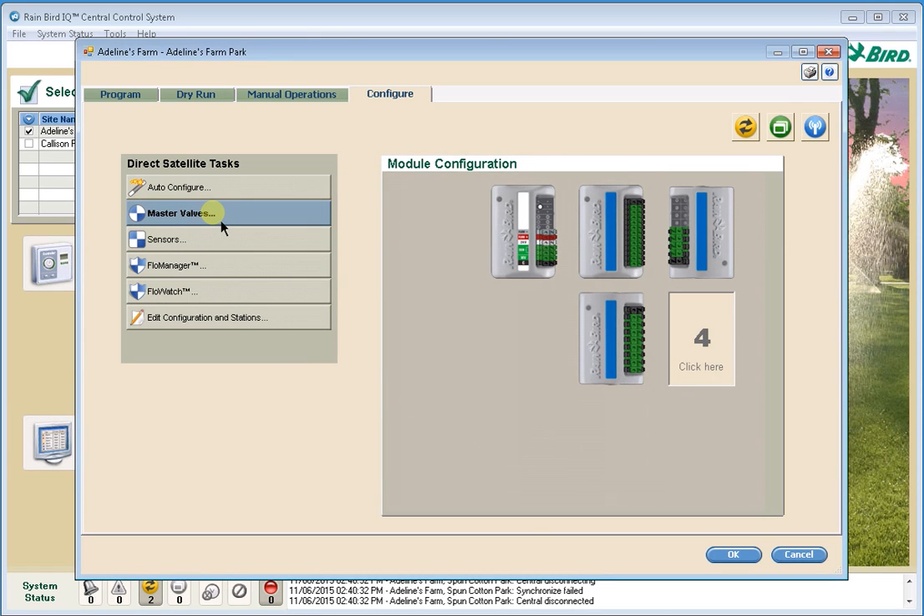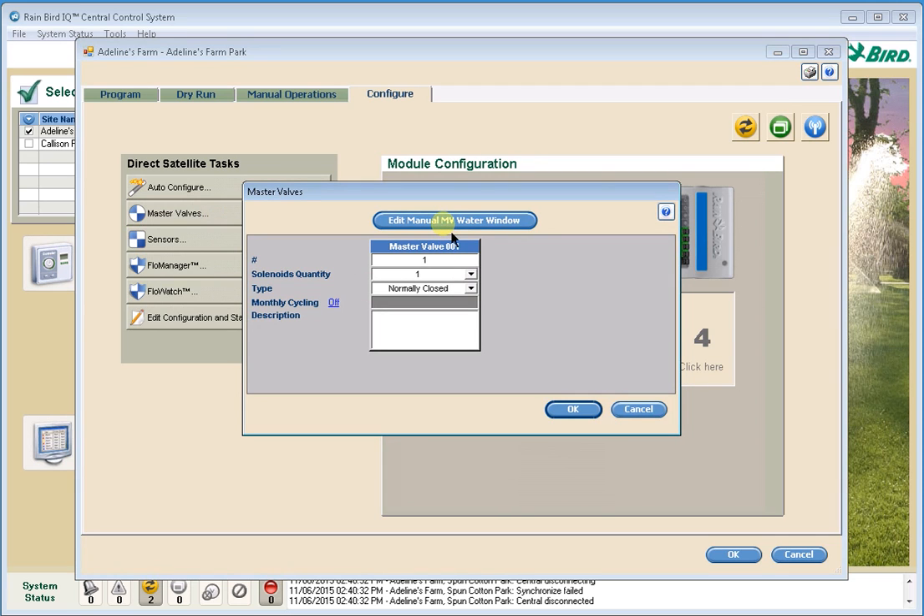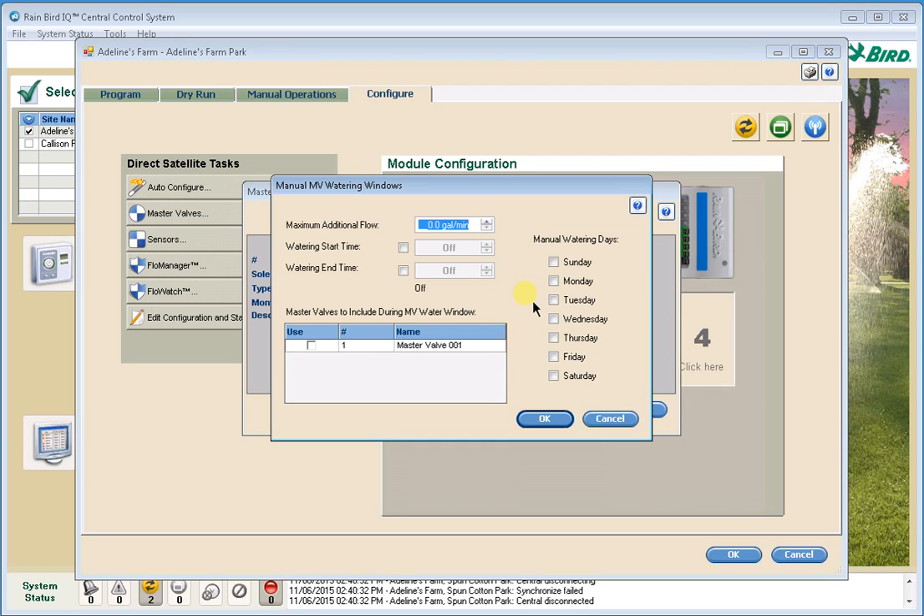One other thing to point out is under the Master Valves setting, there's a button for Edit Manual MV Water Window. Here we have the opportunity, if you have quick coupling valves or manual watering taking place off the main line of your irrigation system, to put in an additional flow rate to allow for that use. We can also set different times of day for it to allow that manual watering. So if maintenance people are on site from 8 a.m. to 4 p.m. Monday through Friday, I can tell it to open master valve one at 8 a.m., allow 20 gallons per minute during those hours, and then close the master valve at 4 p.m.